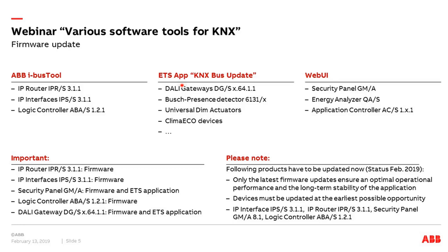There are at the moment three different solutions. One is updating via the ABB i-busTool — covering the IP router, IP interface, and the logic controller. Then we have the ETS app called KNX bus update, which now supports more components: the DALI gateway, bus presence detector, motion detector, the new universal dim actuator, LED dim actuator, many ClimaECO devices, and more in future. Additionally, some components with a web user interface — the security panel, energy analyzer, and application controller in the ClimaECO range — use the web UI for firmware updates.